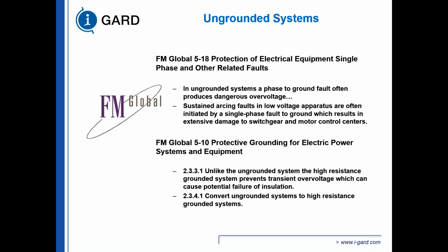FM Global says that ungrounded systems that phase to ground fault often produce dangerous overvoltages. Sustaining arcing faults in a low voltage apparatus are often initiated by a single phase to ground fault, which result in extensive damage. Again, reinforcing the fact that ungrounded systems are not good. And it just goes on, unlike the ungrounded system, high resistance grounded system prevents transient overvoltages. You do get overvoltages in a high resistance grounded system, but they're limited to 173%.